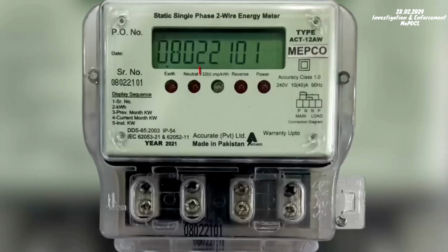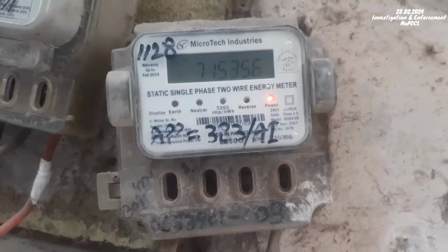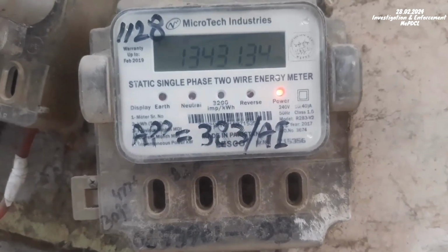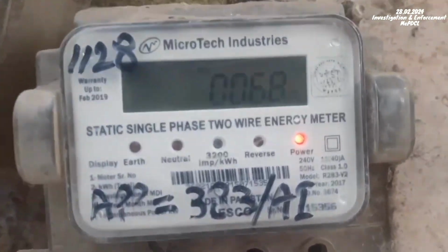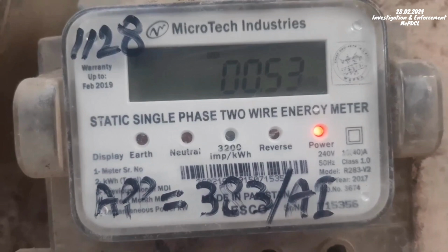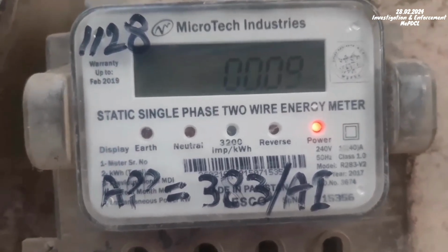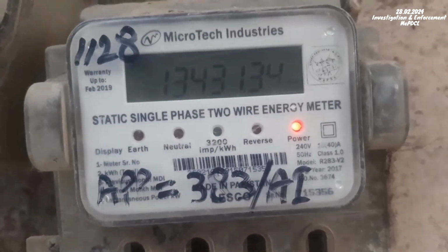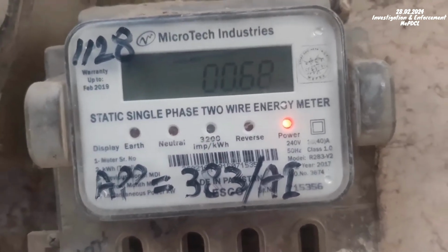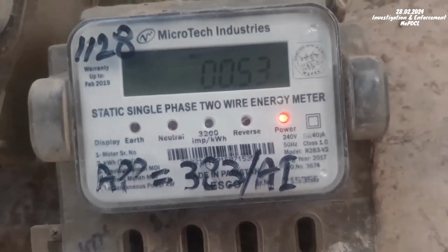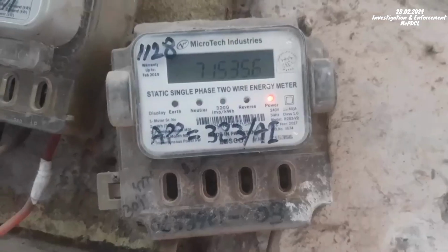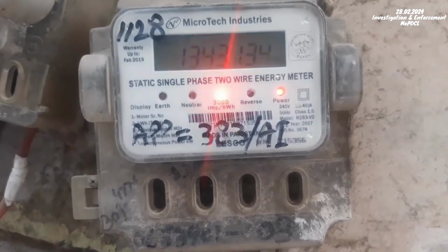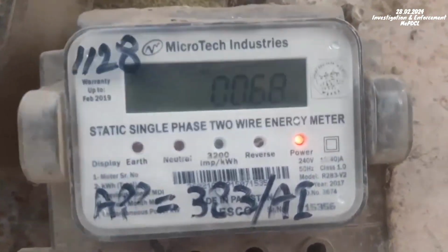So this is what happens in your single phase energy meter. And then, okay, we'll look at this. This is always there, it's simply the meter constant, we say, or the impulse constant. It is in our case 3200 impulses for every kilowatt hour. For example, in this energy meter, simply to indicate that for every unit of electrical energy consumed, the LED will blink 3200 times, to indicate that 1 kilowatt hour or 1 unit of energy has been consumed, right? So it will blink 3200 times like this.